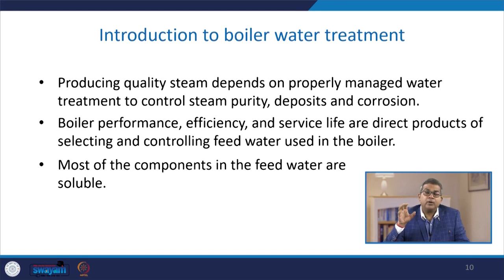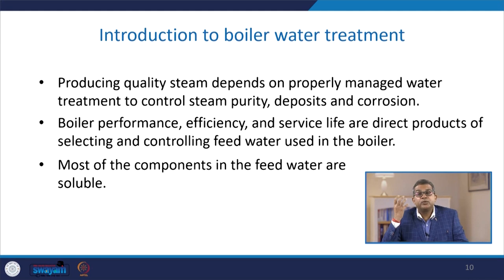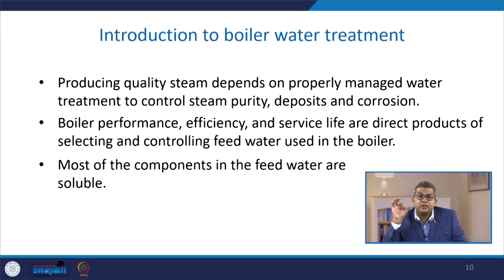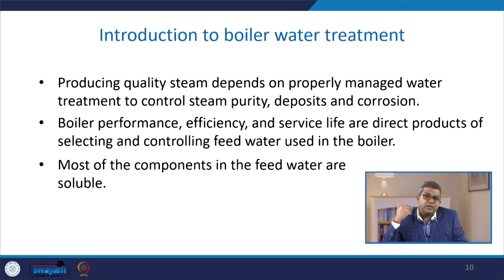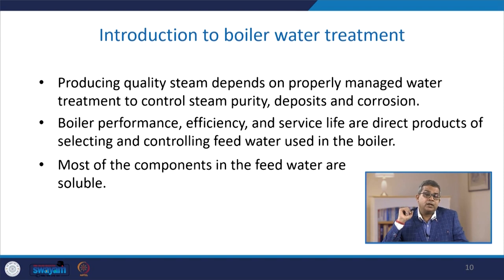When we talk about scaling parameters, flow fluctuation, and corrosion attributed to scales and tube damage, the boiler performance, efficiency, and service life are direct products of selecting and controlling the feed water used. Sometimes ions, dissolved gases, etc. may produce scales and foams, which have no heat value, so efficiency and performance may go down and you may not get the desired steam.